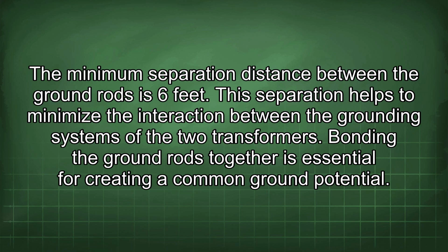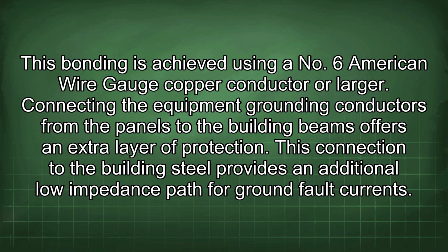The minimum separation distance between the ground rods is 6 feet. This separation helps to minimize the interaction between the grounding systems of the 2 transformers. Bonding the ground rods together is essential for creating a common ground potential. This bonding is achieved using a 6 American wire gauge copper conductor or larger. Connecting the equipment grounding conductors from the panels to the building beams offers an extra layer of protection. This connection to the building steel provides an additional low impedance path for ground fault currents.